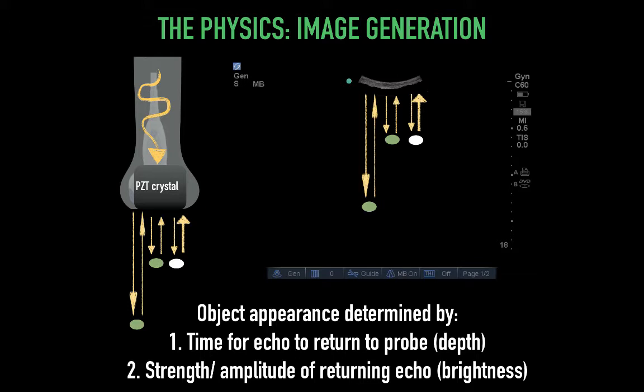Object appearance is determined by the time for the echo to return to the probe (depth) and the strength or amplitude of the returning echo (brightness). The vertical position of the echo pixel on screen is based on the time delay between emission and return of the ultrasound beam. Velocity is assumed constant within soft tissue, so quickly returning echoes reflect superficial structures and slowly returning echoes reflect deeper structures. The horizontal position is based on the receiving piezoelectric crystal's location along the transducer. This horizontal and vertical pattern of dot brightness and positioning creates B-mode, or brightness mode, often called the 2D image.